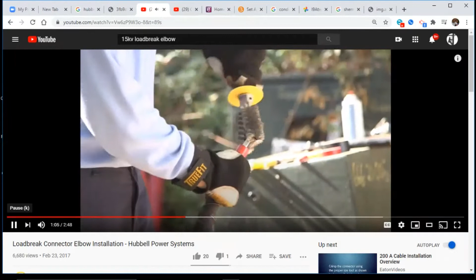Use a wire brush to clean the exposed conductor. Place the compression lug on the conductor and rotate to spread inhibitor. Make sure to align the flat threaded side with the bushing interface. Crimp the lug to the conductor, starting just below the knurled line and rotating. Okay, so when you get this insulation cleaned off and you start crimping, where do you crimp? From top to bottom or bottom to top? Bottom to top.